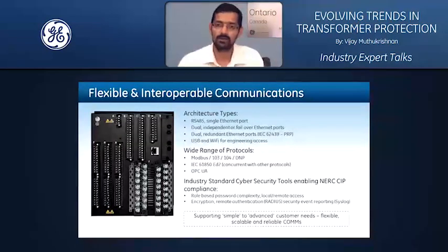On top of that, for general engineering and maintenance access, you can have a simple USB port or a very useful and powerful Wi-Fi mechanism. Many customers may think Wi-Fi is too far-fetched for a protection relay. But when you look into the application scenarios, you can deploy Wi-Fi. Think of it from a safety perspective: an operator need not go near a protection relay to pull information and records, and everything is easily possible. Or if you're doing a factory acceptance test or a site acceptance test, you can have simplified configuration and set up everything using Wi-Fi access from a laptop. That's the power of functionalities like Wi-Fi.